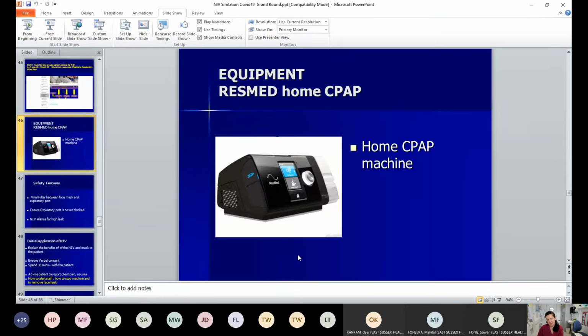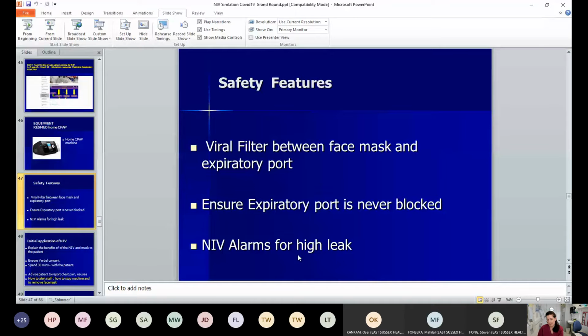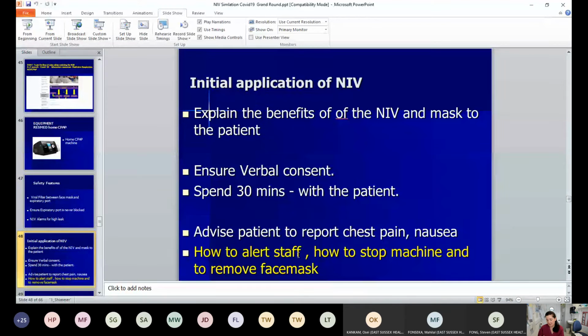The standard CPAP machine that patients use at home looks like this, so it looks slightly different, and that only does CPAP. And the safety features on our ventilators are that they do alarm if there's high pressure or there's a leak, and our nurses are doing checks every hour to make sure that the expiratory port doesn't become blocked. So when we start off NIV, we will be spending quite a lot of time with the patient to explain the benefits that it's going to give them.